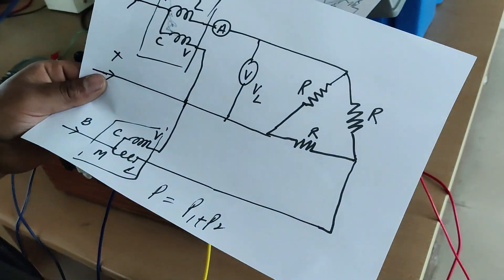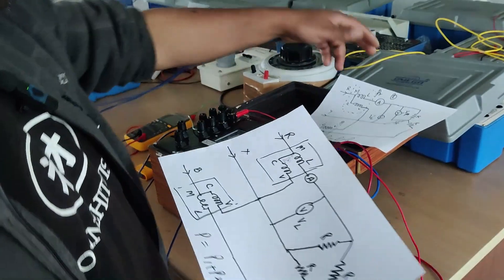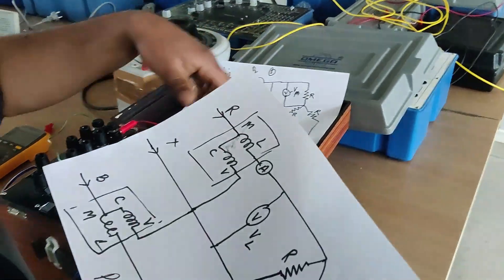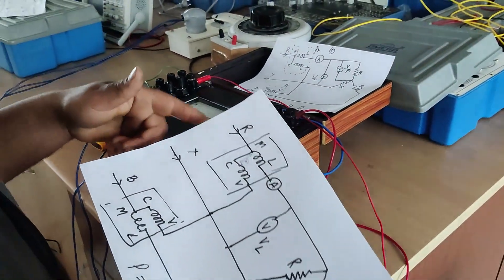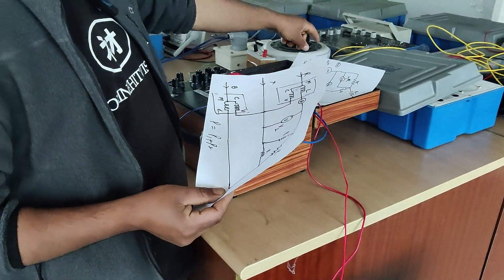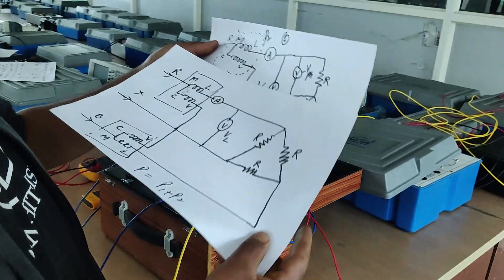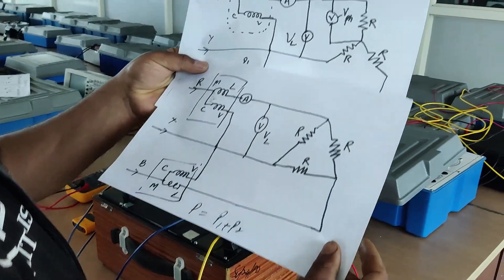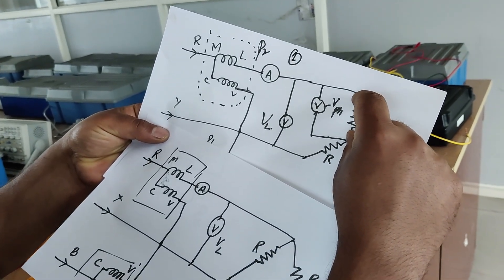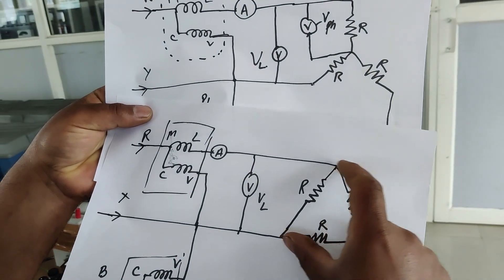We will have the same resistance R in each phase of the load bank. The same resistance will be connected first in star, then in delta, and we will verify the amount of power consumption. In case of delta it must be three times that of star. In star connection, the phase voltage appears across the resistance. But in delta connected network, the line voltage appears across the resistance.